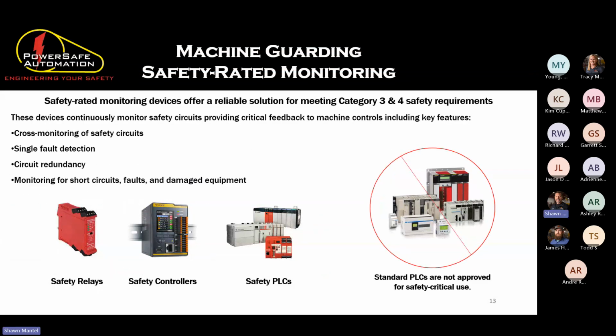The thing to be careful of, standard PLCs are not approved safety devices. So when someone says, I have a PLC, every machine should either have relay logic or PLC. That is what's telling the machine how to operate the machine itself. That's not telling it to operate safely. A safety PLC is telling it to operate safely. So if they say, I have a PLC, do you have a safety PLC or do you just have a PLC? If it's just a PLC, that is just your computer telling the machine how to run. Safety PLC, safety controller, safety relay is what is required to do the checks to make sure you are running safely.